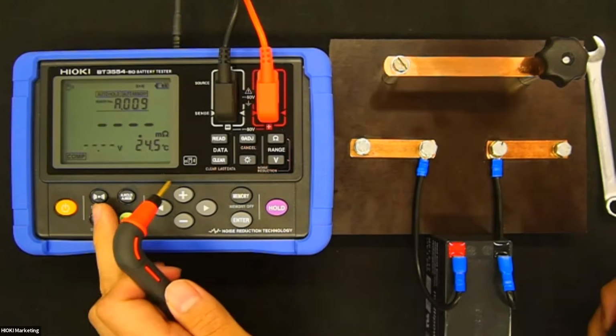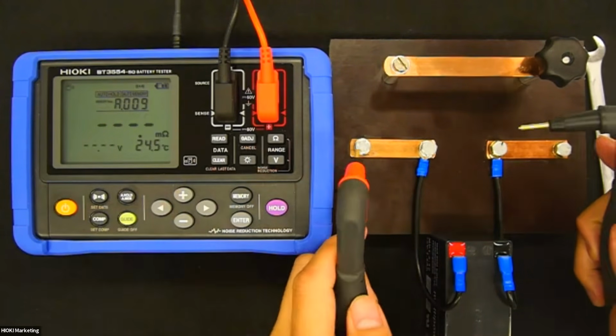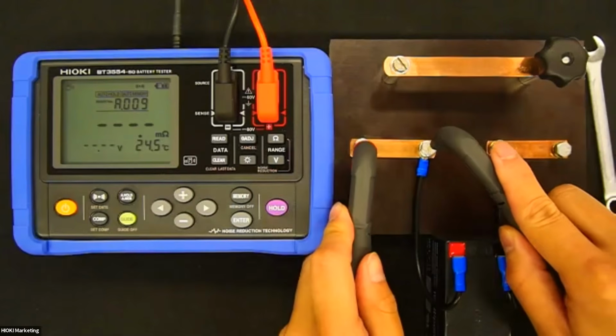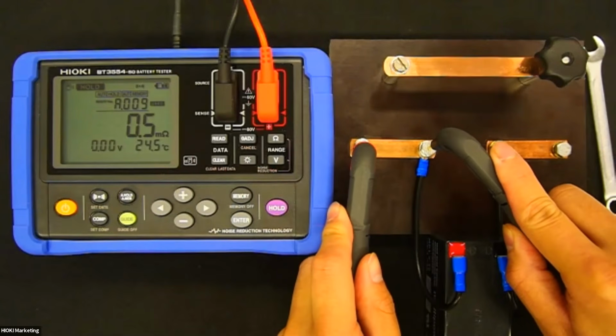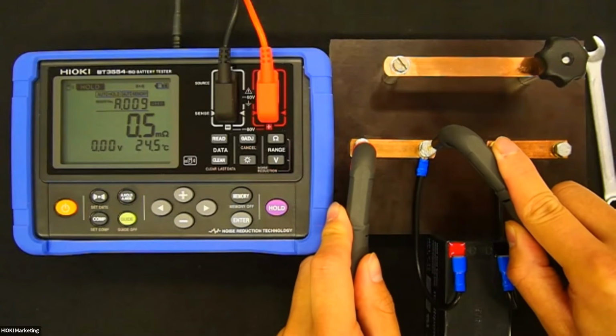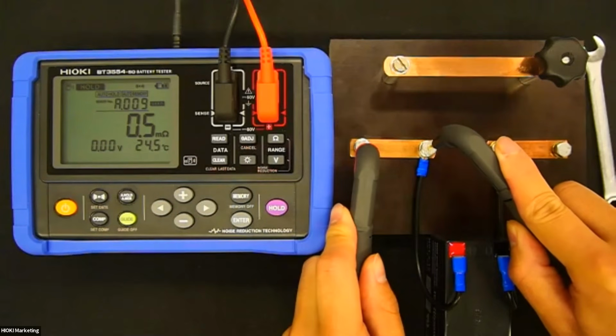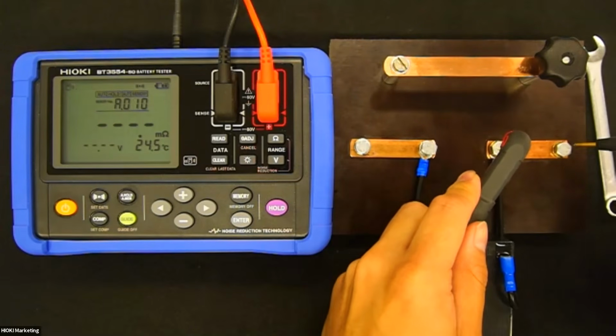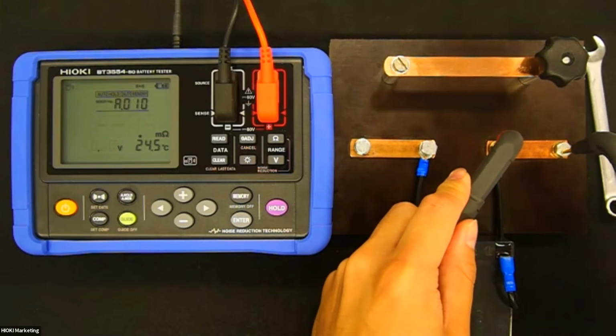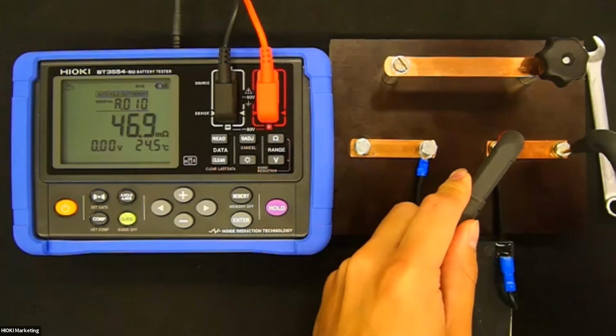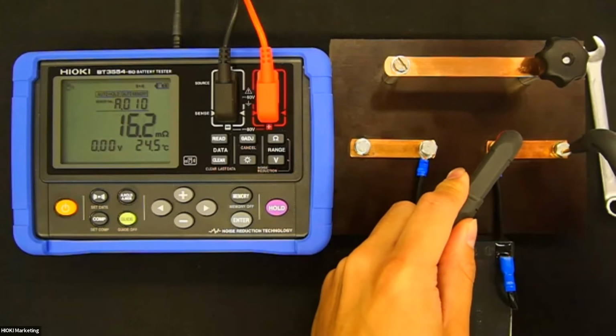So let's check the connection resistance using the battery tester. This side shows 0.5 milliohms, which is a very good condition. But how about this side? Now it's not stable because the bolt is loose. We get 16.2 milliohms, a completely different value.